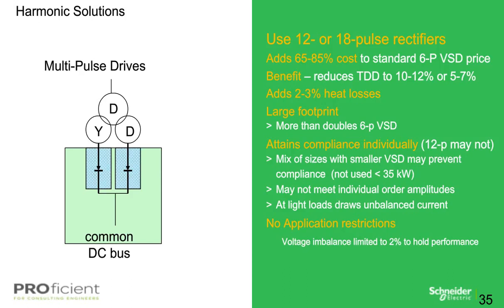So if we take a look at a 12-pulse configuration, it employs 2 rectifiers of any design and a transformer, auto or isolation, which has 2 secondary windings with a 30-degree phase shift. When applied to a single load, every other odd pair of harmonic orders is greatly reduced. This begins with the 5th and 7th harmonic order. A 12-pulse system can attain 12% THDI, typically per load.